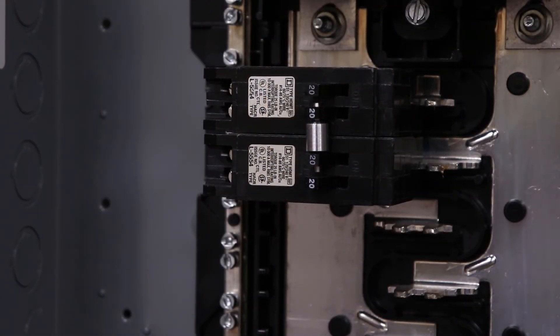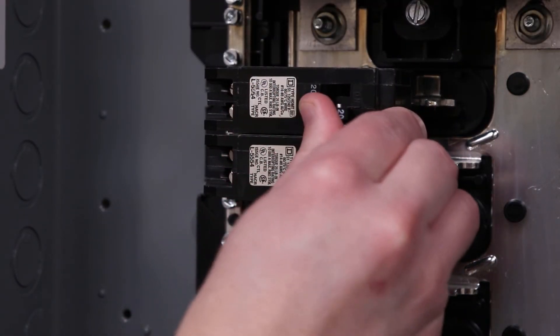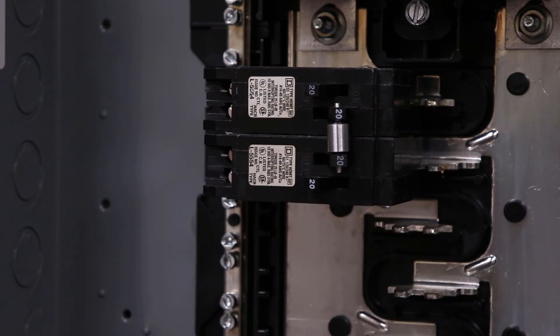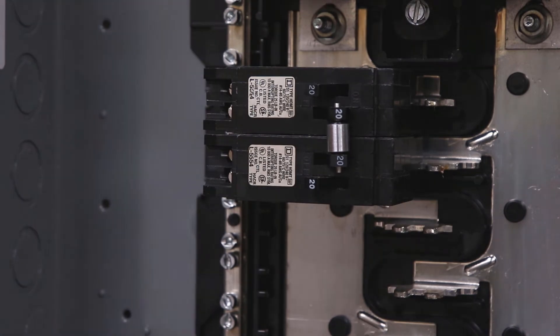You now have your handle tie installed to provide common switching of the inside two handles. Keep in mind that this is common switch only and will not provide common trip.